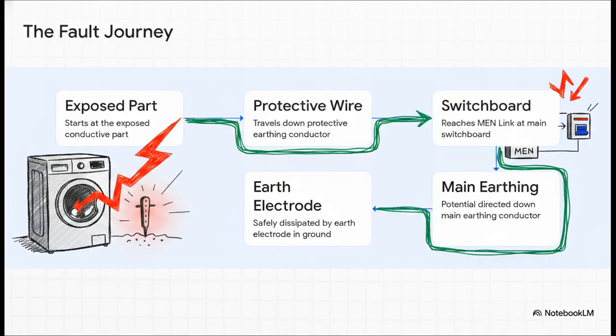Let's move to the next step and see how this builds, literally tracing the exact journey of a fault current through this network. So it starts at the exposed conductive part, our trusty metal washing machine. The current rushes down the protective earthing conductor in the wall, boom, arriving at the main switchboard. Here, the MEN link allows a massive surge of current to just dump into the neutral, instantly tripping that circuit breaker. And simultaneously, any excess potential gets directed down the main earthing conductor, safely dissipating out into the ground via the earth electrode. It's brilliant.